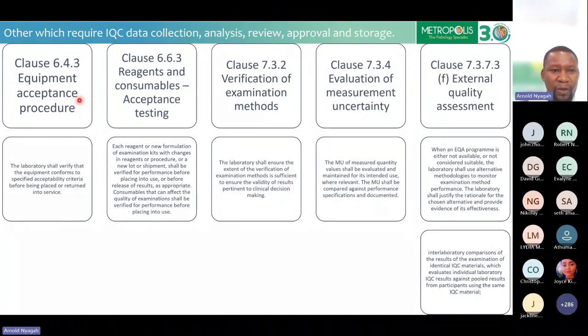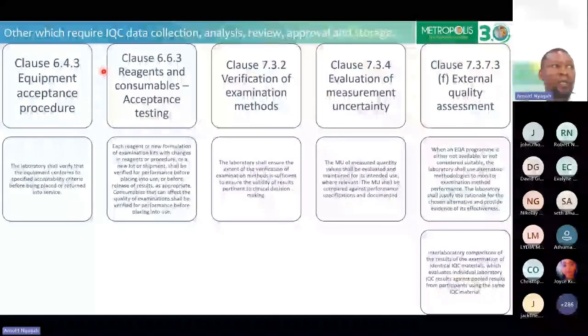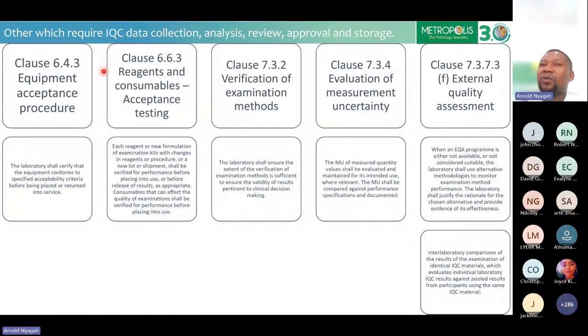Also on reagent and consumables acceptance testing, which we commonly call lot-to-lot verification, you can use your IQC to check lot-to-lot verification. I changed a lot 5 minutes ago and ran QC. I have the IQC data for the previous lot, so I can compare. If I've set my rules appropriately in the system and it does not fail, I know the acceptability has been met.